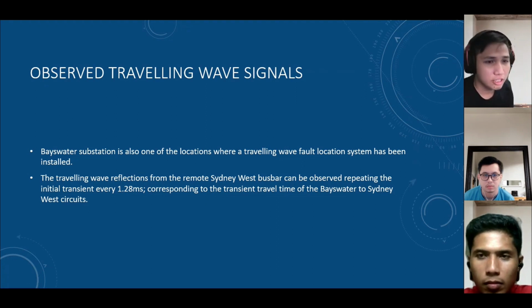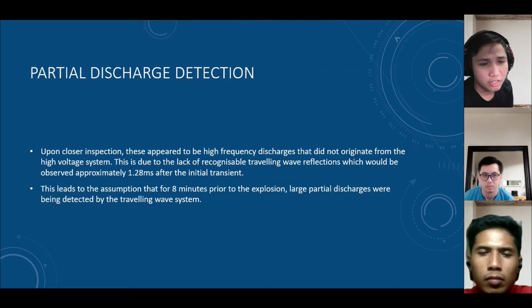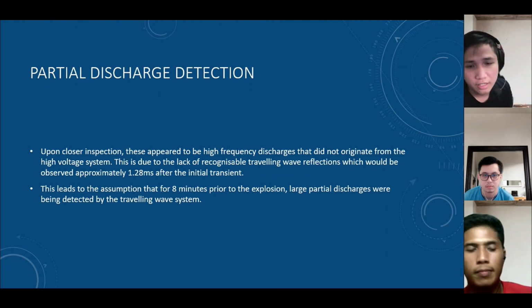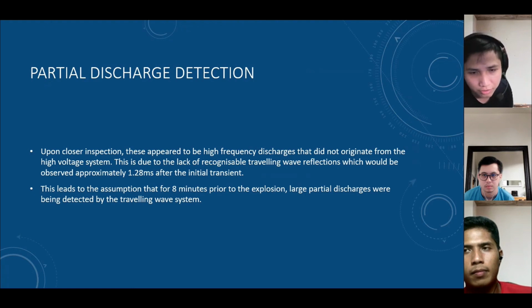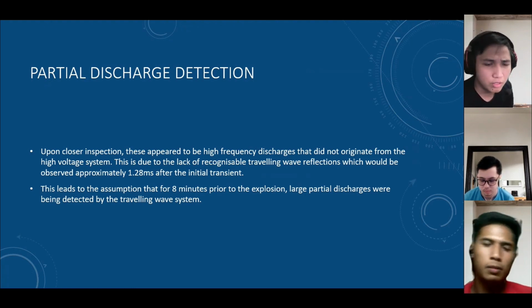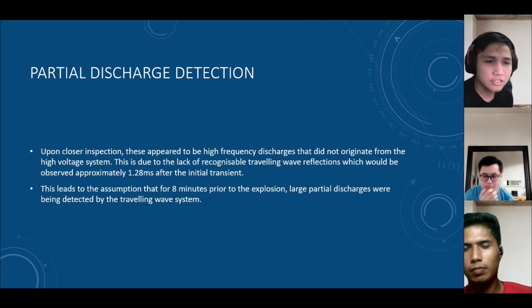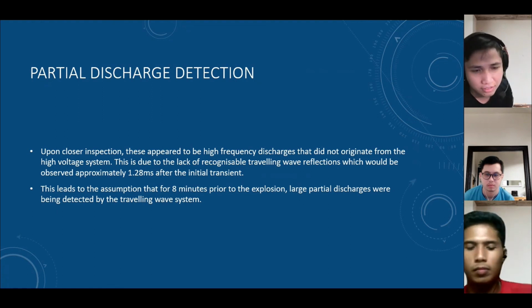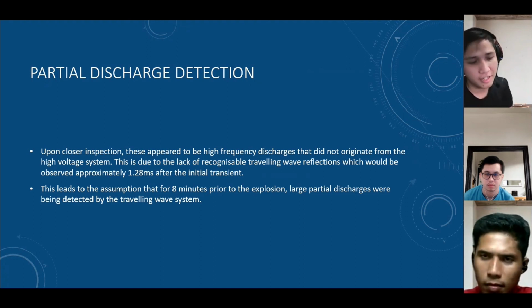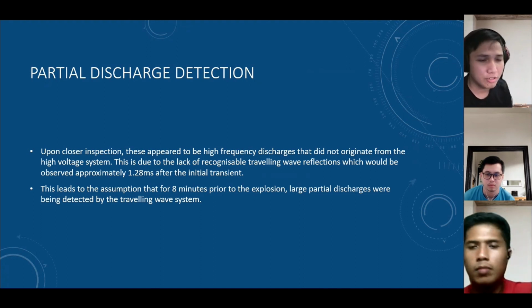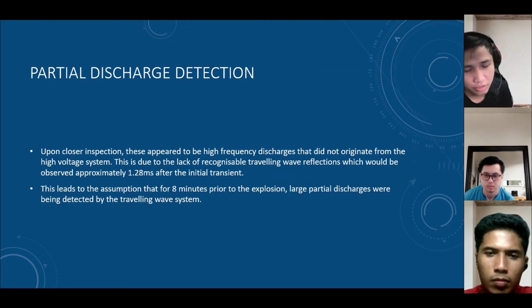All right, the second one is partial discharge detection. Upon closer inspection, this appeared to be high frequency discharge that did not originate from the high voltage system, due to the lack of recognizable traveling wave reflection, which would be observed approximately 1.28 milliseconds after the initial transient. So when the failure occurs, there will be a discharge in the transformer. This will detect the initial condition and alert the controller system.